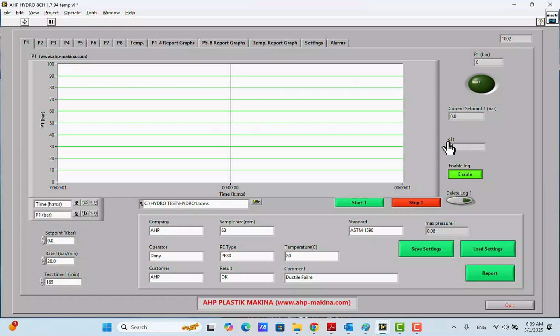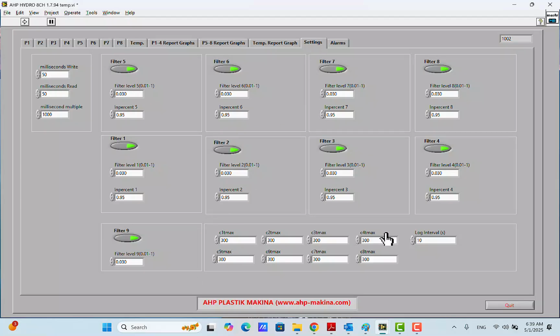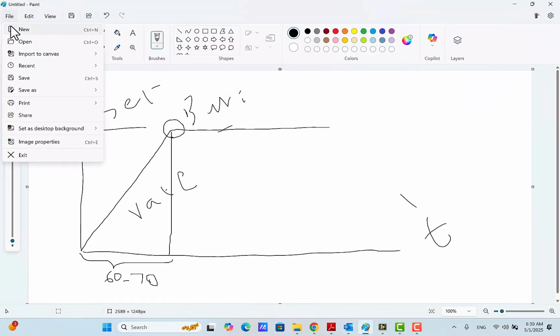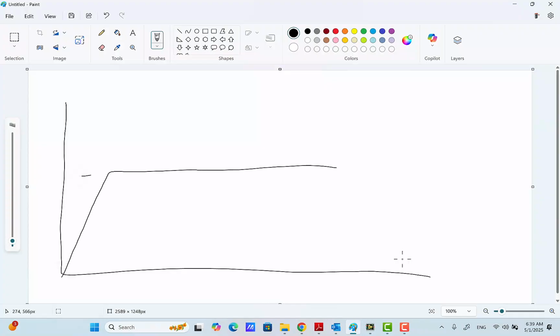That's why you need to set the C1T max time here. For each line, you have a C1T max time. This is in terms of seconds. Let me show it here. Suppose that you had a sample working with a set pressure of 30 bar. Suddenly, something happened on the sample and it burst, the pressure drops, and here the pump starts working, but the pressure is not rising, and of course will not get to the set point, that is 30 bar.